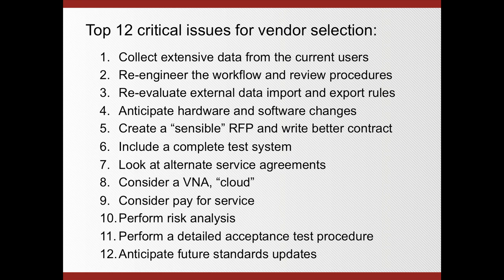Do you have a strong biomedical engineer in your department that you could send to school to take some classes and learn about supporting the system to a different level, so that you don't always need the high-end service agreement from your vendor? If you look at the literature, you find that large institutions that really focus on this are able to save literally millions of dollars annually by taking some of the service agreements out. Or, as another alternative, outsource to third-party service providers.